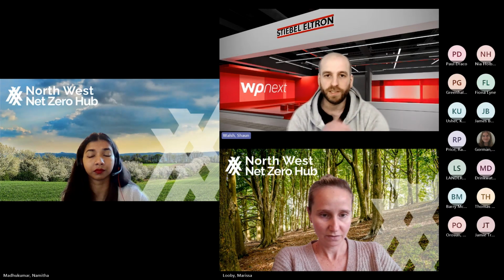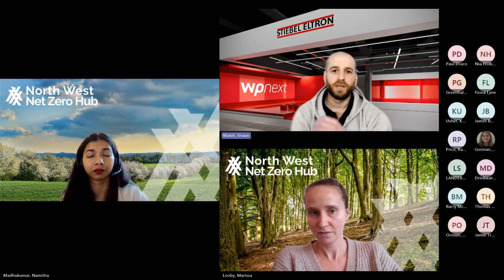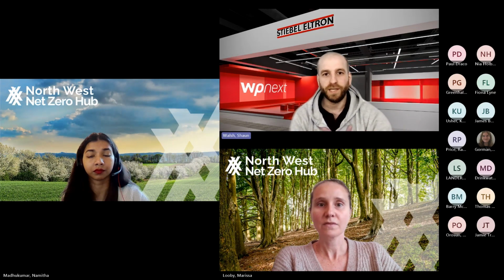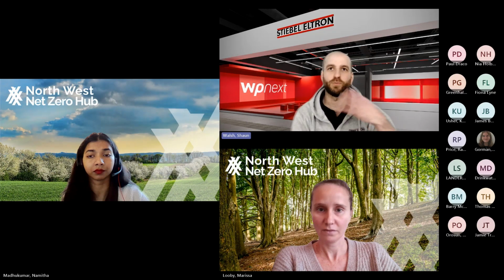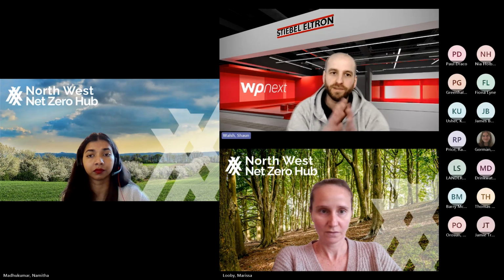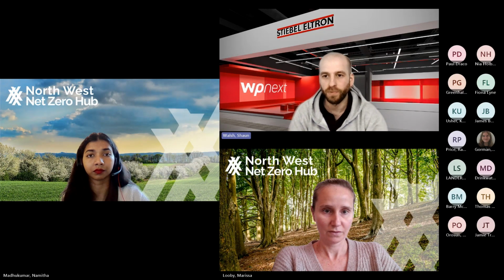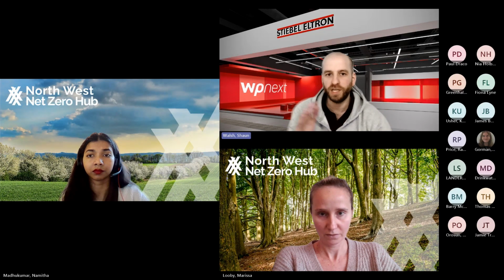As an example of something you should check on your servicing, a real world example: I had a heat pump installation. Someone went to service it, and during that period a new electric cooker had been installed, and someone had swapped the MCB for the cooker with the heat pump, and it caused issues. So you should always check your breakers and make sure they're the correct ones. Yes.